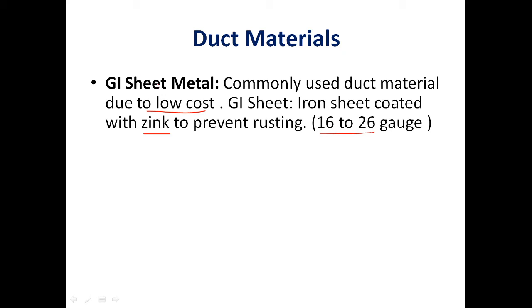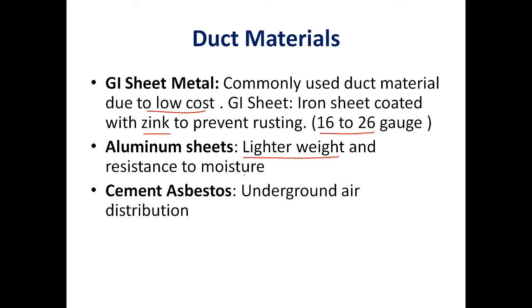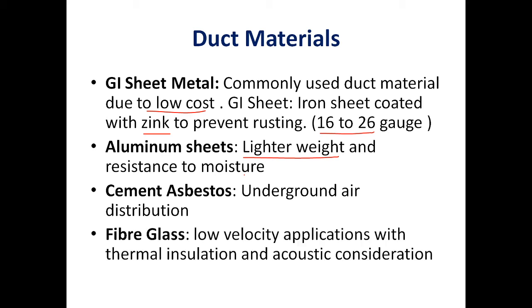Aluminum sheets can also be used, taking advantage of their lighter weight and natural resistance to moisture without any coating, though they are costlier than GI sheets. Other duct materials include cement asbestos, used in underground distribution for its high strength, and fiberglass, used for low-velocity applications where reduced heat transfer and noise reduction are required. Fiberglass is a poor conductor of heat, limiting heat loss or gain, and it also absorbs noise.